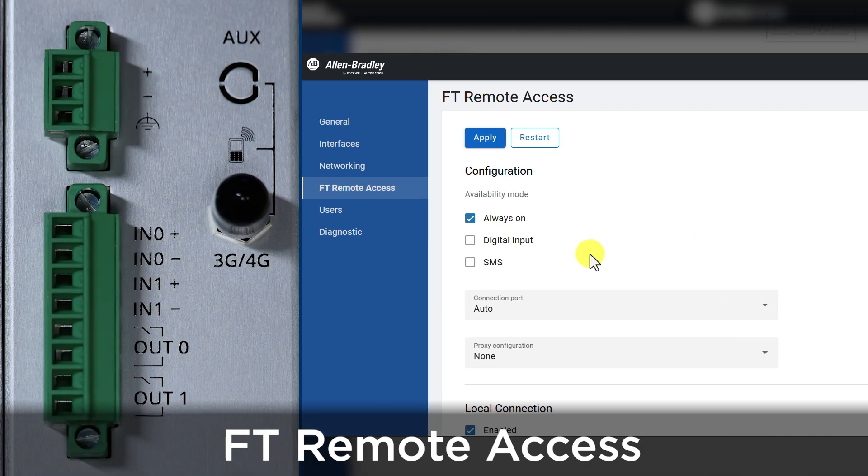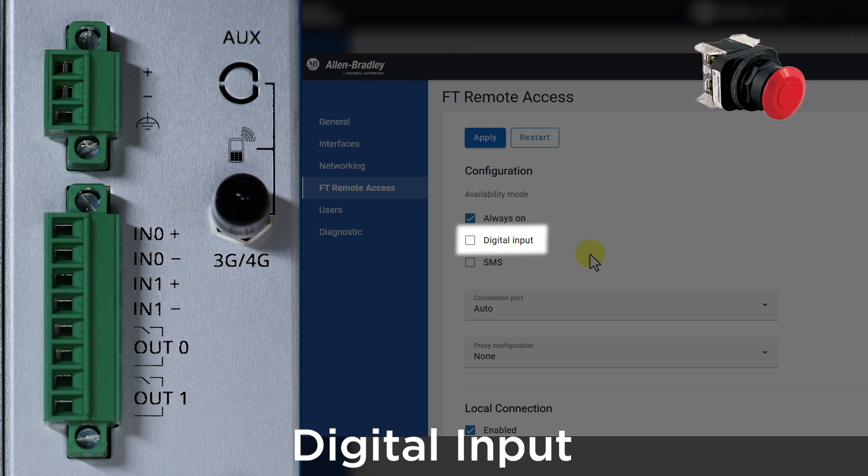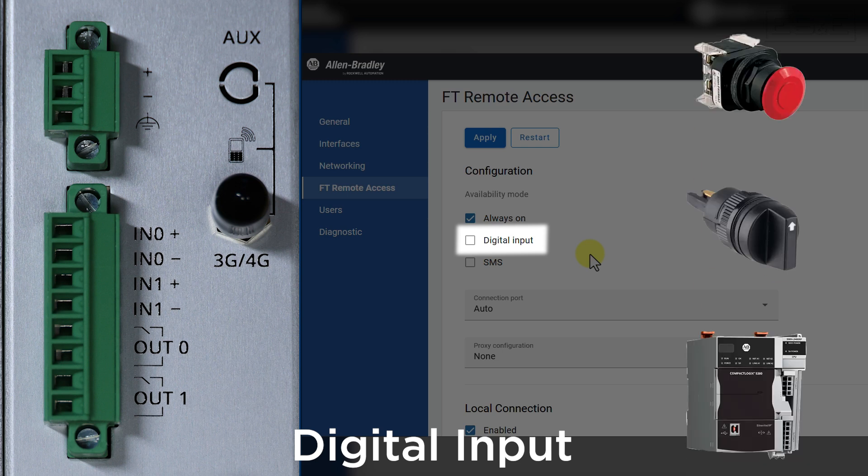The server connection on the 4300 is also configurable to use a digital input, which means you can have something physical at the equipment such as a button, selector switch, or even a PLC output to enable the remote server connection.